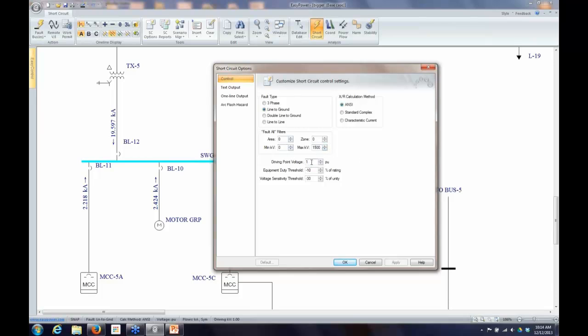The Driving Point Voltage is basically the pre-fault voltage. The default is one per unit, so for a 480-volt system it starts at 480 volts. If you're doing arc flash calculations and your system always runs high or low, you may want to adjust this, because increasing the driving point voltage by 1% will increase the fault current by approximately 1%. For arc flash or equipment duty, the driving point voltage should match the maximum expected system voltage.